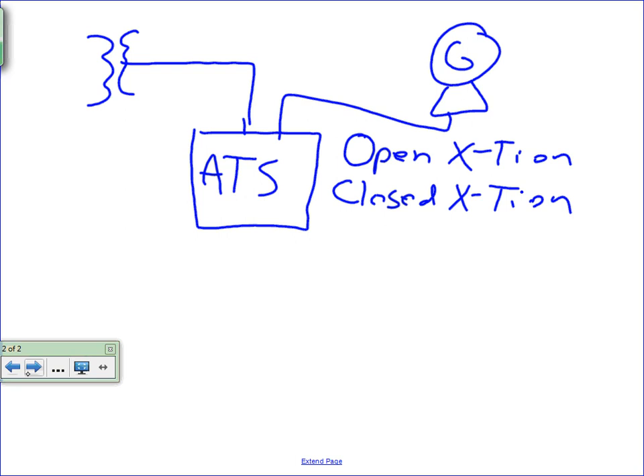Because all of a sudden the ATS senses that the utility's back. In an open transition, it will actually disconnect the generator and then connect to utility, so you get a blip in there, a loss of power on the retransfer as well. Okay, on a closed transition, for just a few cycles, right?